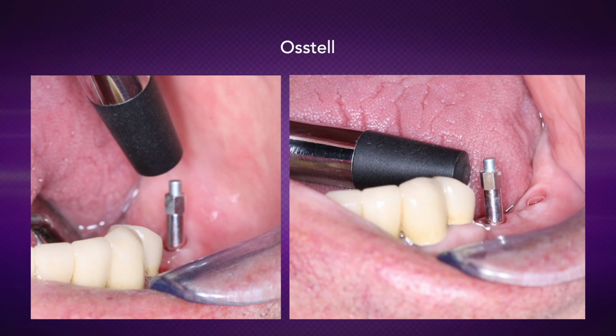Does one concept have advantages over the other concept? Each has unique advantages. The impulse testers that tap on the implant seem to be more versatile. They can be used on the healing abutment or on any other abutment, even on a temporary restoration on the implant. The resonant frequency analysis devices are more precise and more accurate because you have to unscrew the healing abutment, attach the calibrated peg, and this gives you a very precise reading. So both have their advantages.